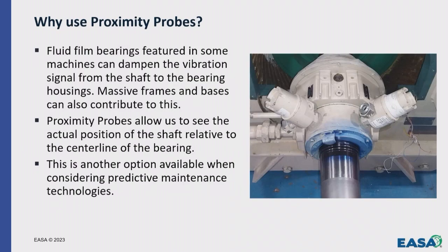So why would you want to use a proximity probe instead of just an accelerometer or something like that? Typically you're going to find them used in machines that have fluid film bearings, and part of the beauty of a fluid film bearing is we have that nice oil film. It provides cushion. We don't have actual contact in an ideal situation anyway between the bearing surface and the shaft. And so that's great. It provides for excellent reliability, longevity of the machine, but it also dampens the vibrations experienced by the rotor a little bit.